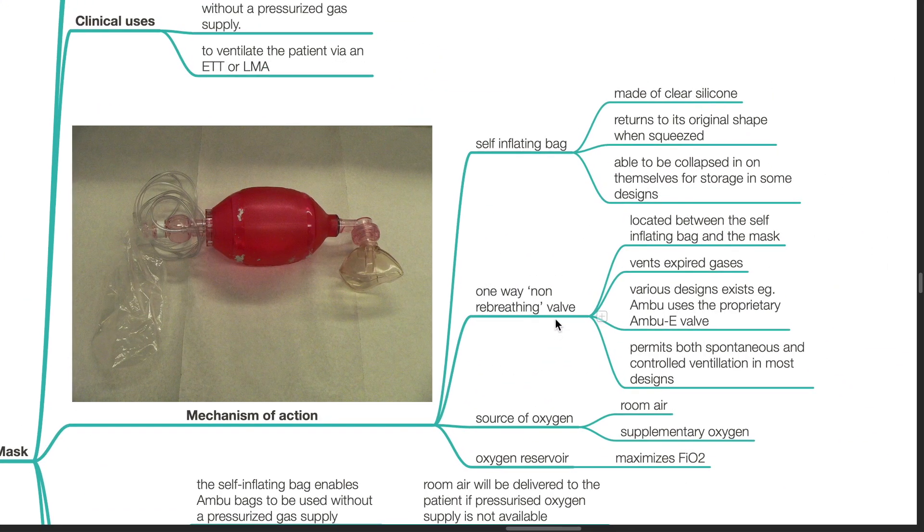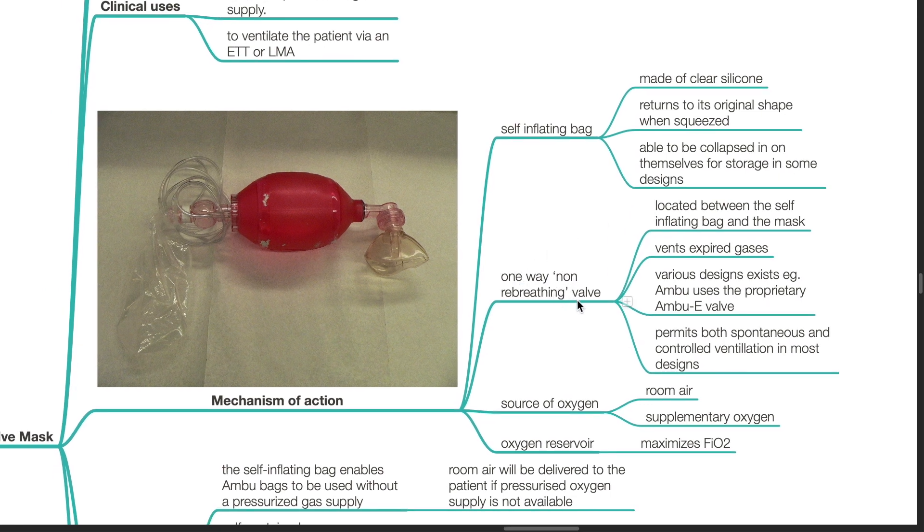Mechanism of action. It has a self-inflating bag made of clear silicone that returns to its original shape when squeezed. There is a one-way non-re-breathing valve located between the self-inflating bag and the mask that vents expired gases. This valve permits both spontaneous and controlled ventilation in most designs. Source of oxygen can either be room air or supplementary oxygen. Oxygen reservoir maximizes FiO2.